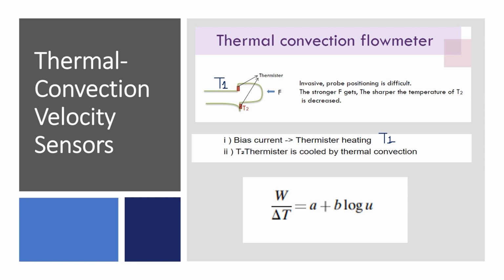The working principle of the thermal convection flow meter is based on the theory of conductive and convective heat transfer. Two sensors are supported either using inline flow bodies or insertion-style probes of the meter. These sensors are then interfaced with the fluid being measured. Heat is introduced into the flow stream of the fluid. A large amount of heat is lost with the increase in the flow of the fluid, and the amount of heat dissipation is measured by using one or both of these temperature sensors.